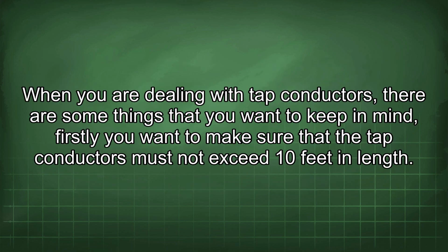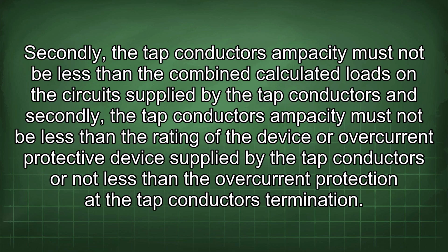When you are dealing with tap conductors, there are some things that you want to keep in mind. Firstly, the tap conductors must not exceed 10 feet in length. Secondly, the tap conductor's ampacity must not be less than the combined calculated loads on the circuit supplied by the tap conductors. And thirdly, the tap conductor's ampacity must not be less than the rating of the device or overcurrent protective device supplied by the tap conductors, or not less than the overcurrent protection at the tap conductor's termination.